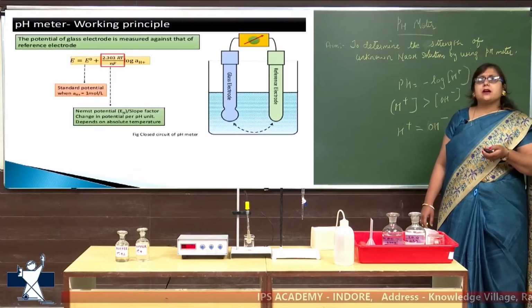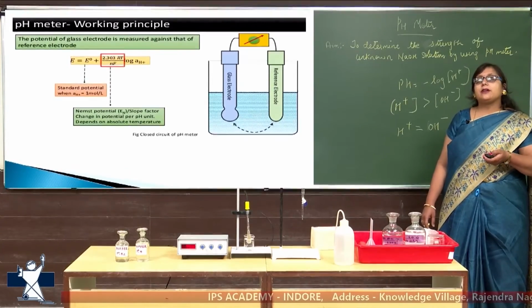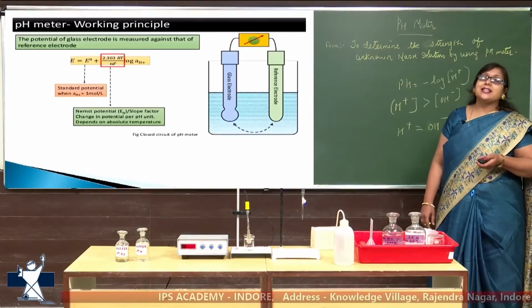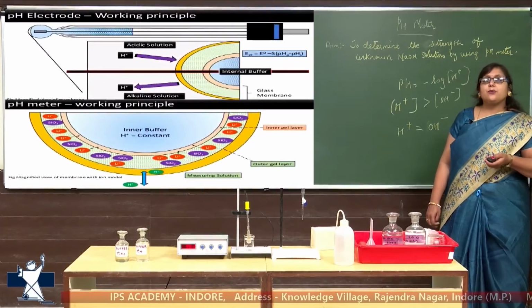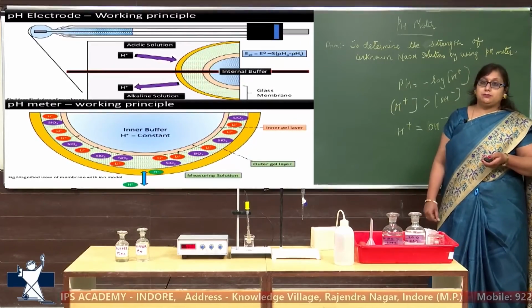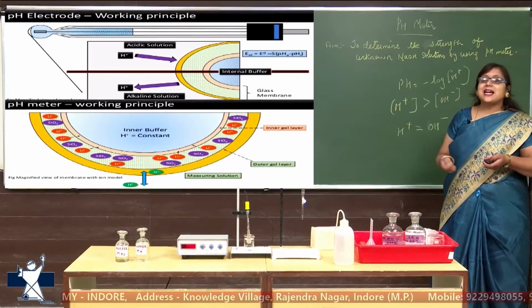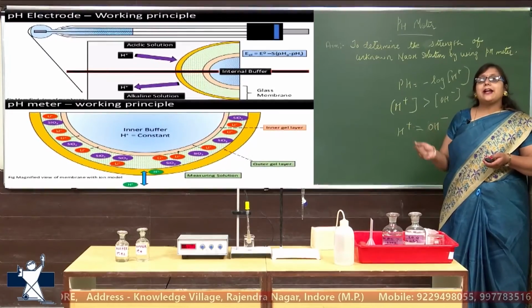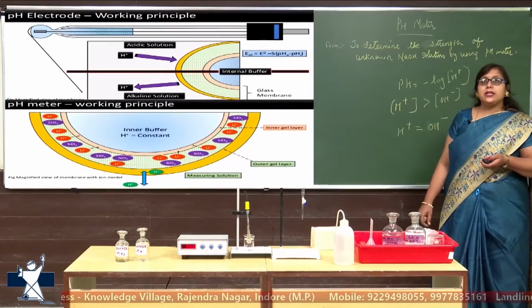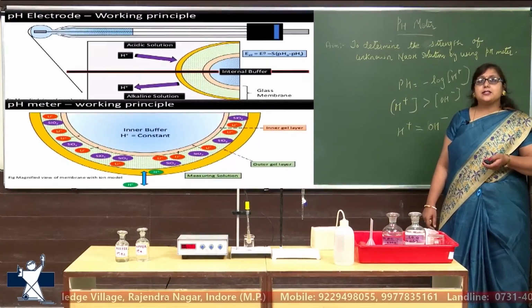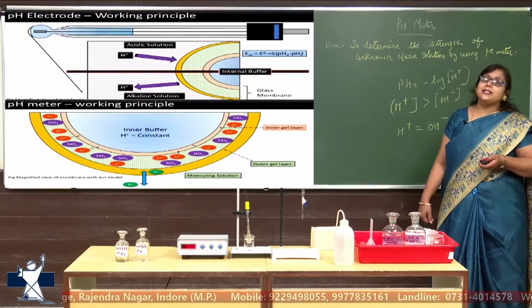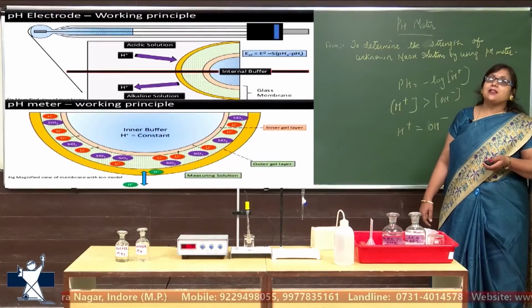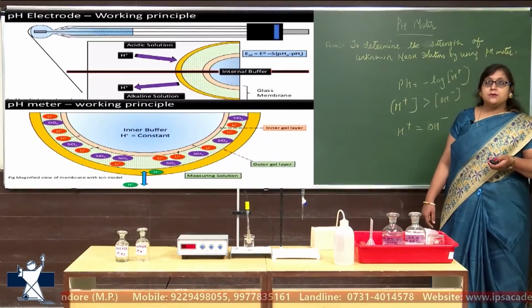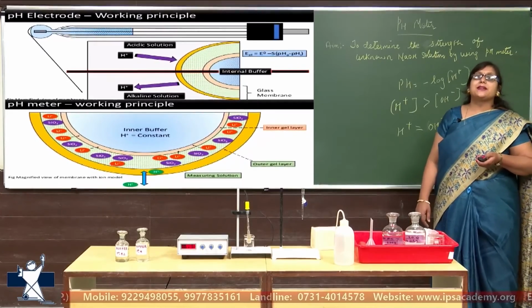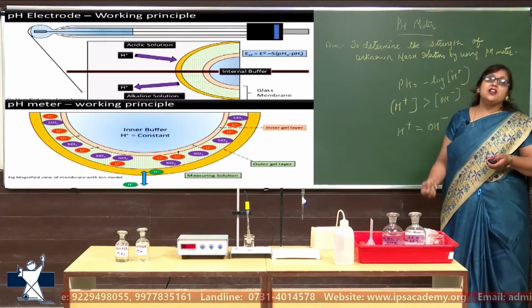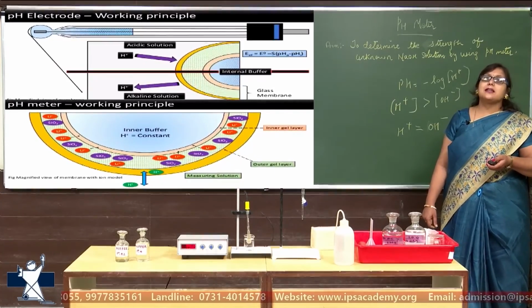This is a circuit in which a glass electrode and a reference electrode are put. When they come in contact, they behave like a battery and start generating electric potential. Basically, whenever the electrolyte comes in contact with the sample, hydrogen ion activity is initiated, and the hydrogen ions surround the electrodes, and there is an exchange of ions with the H+ ions. Due to the difference in the electron mobility of the electrolytes present, they generate a potential, and this potential is displayed on the potentiometer. The electrolytes are present between the inner gel layer and the outer gel layer, and the H+ ion is the only ion which can cross the outer gel layer.